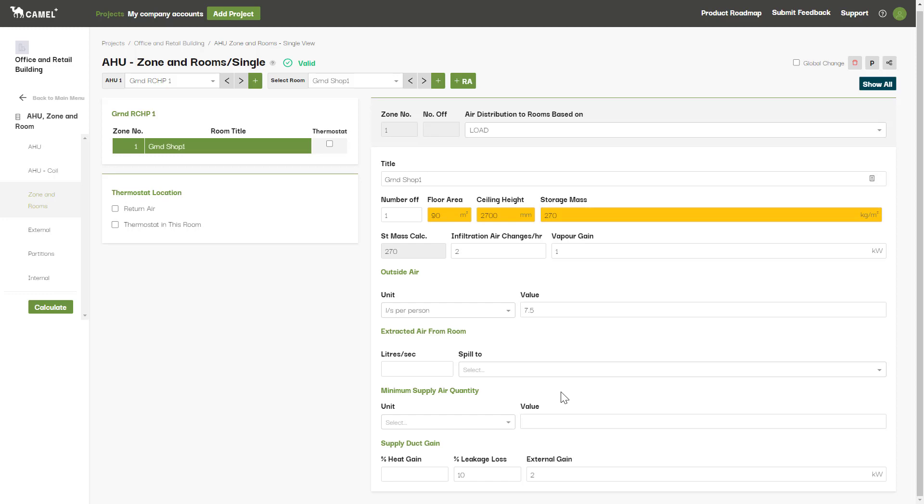This will then increase the amount of supply air going to all the other rooms connected to this AHU as well. Finally, you can enter in your supply duct gain for the room either as a fixed kilowatt heat gain or a percentage of the room sensible heat, and you can enter a percentage for your supply air leakage loss here. More information on these can be found in chapter 7 of the DA9 3rd edition.